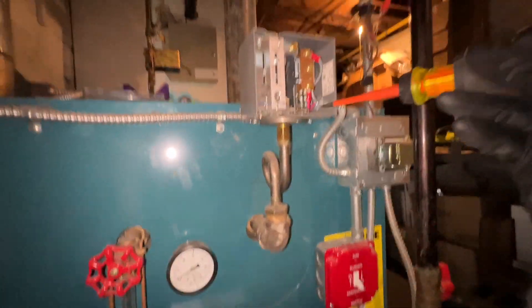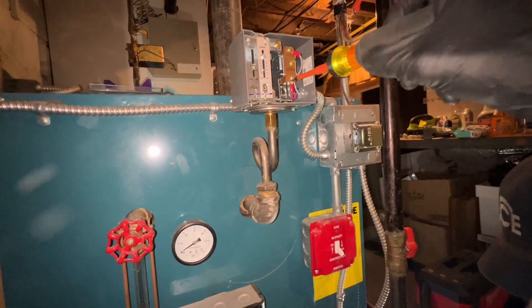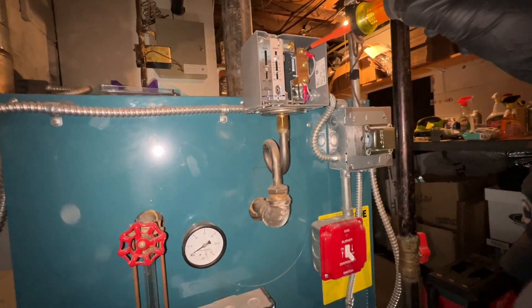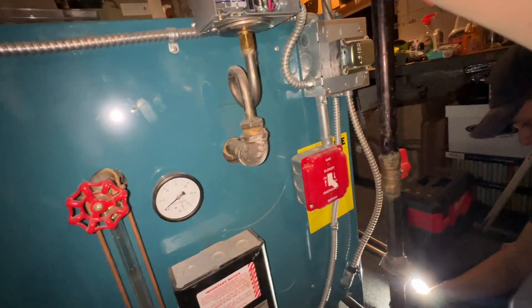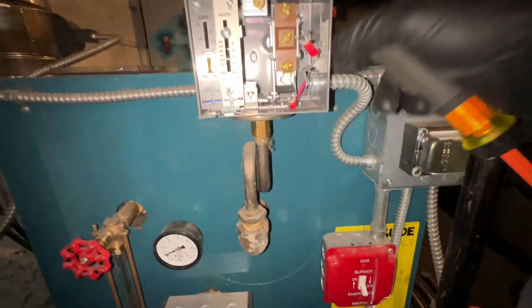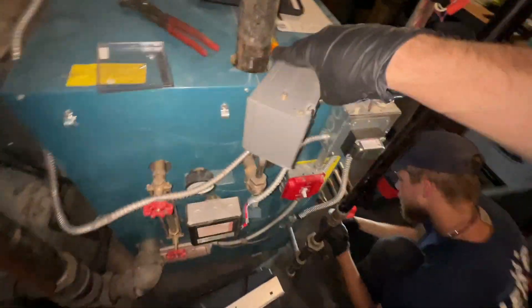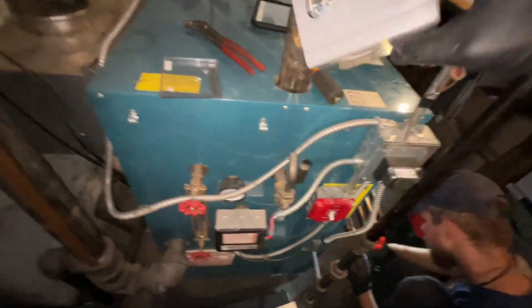Peter's cleaning out the burners and the combustion chamber. I'm disconnecting my wires so I can spin off the pigtail and make sure it's clean. We'll spin off the pressuretrol and make sure the pigtail is clear. Ideally it would be brass, but you can see this one's black, so my guess is it's going to be plugged. Got the wiring disconnected, so you can just spin this loose, put it to the side, and I'm gonna blow through it.